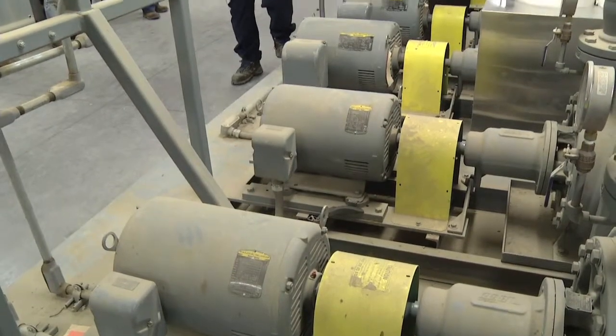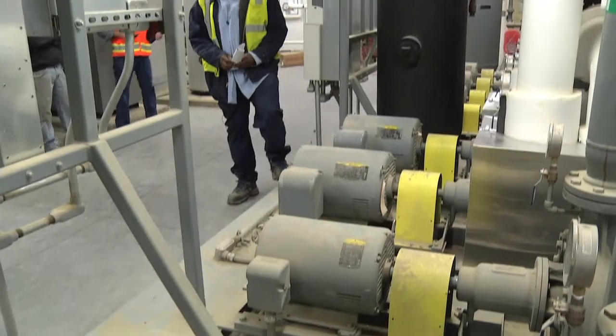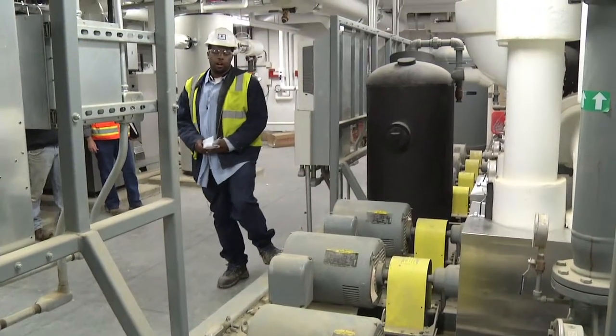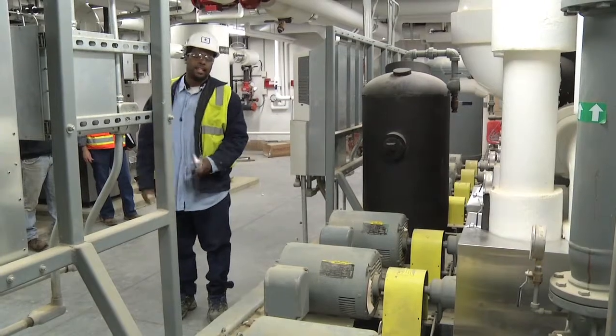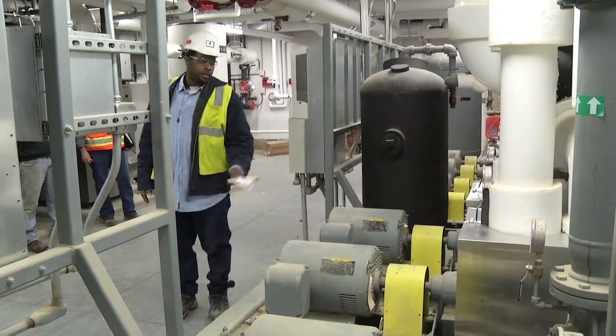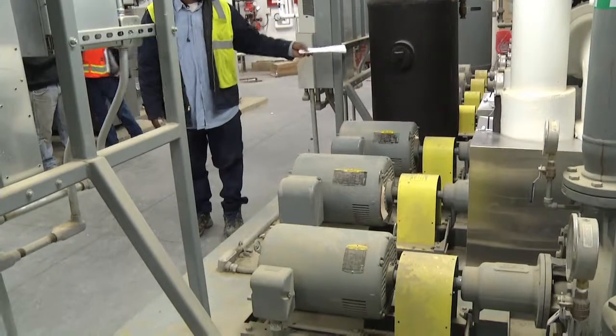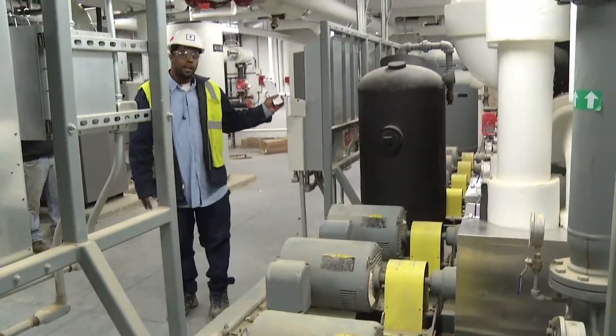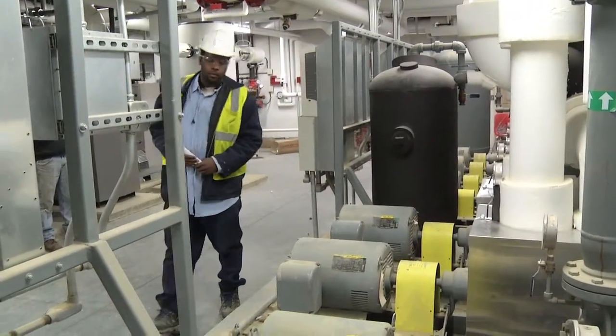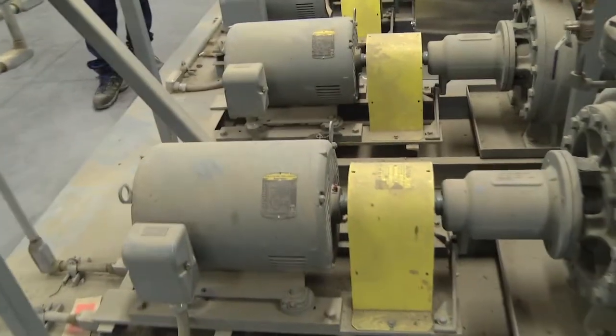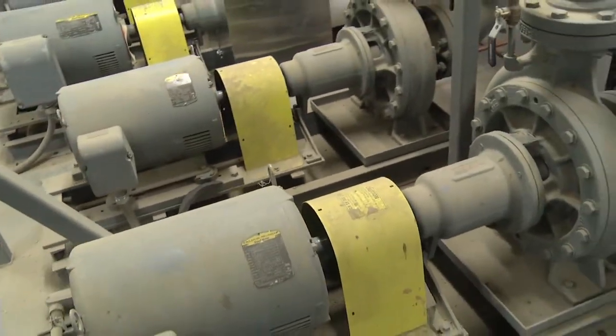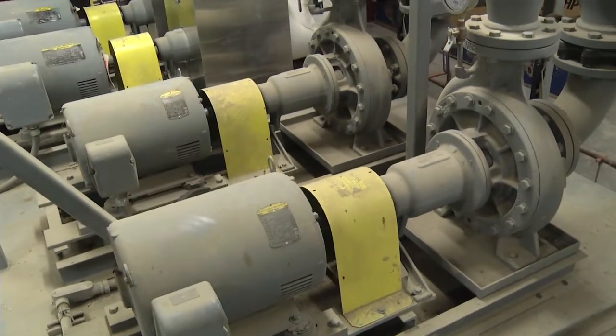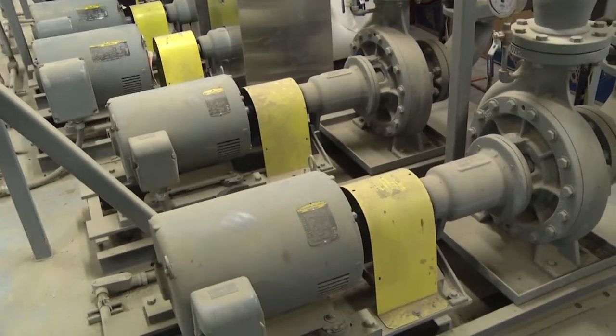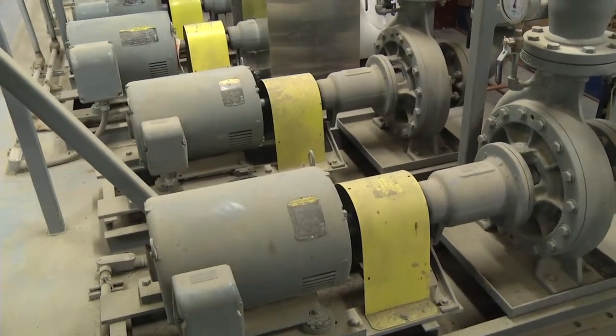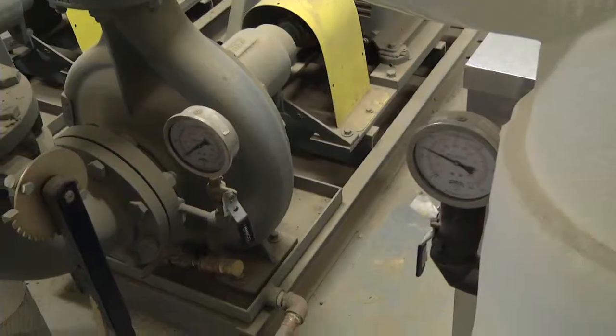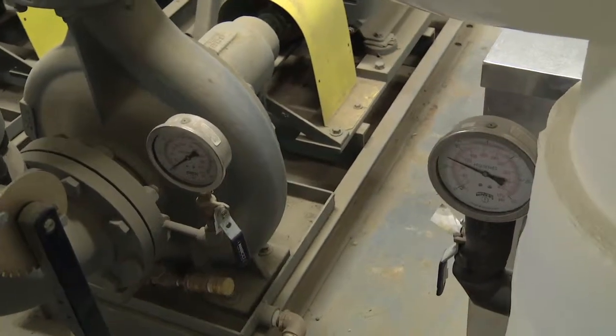And what we're talking about now is your hydronic pump packaging system, which consists of a lead lag, condenser pumps, primary chill water pumps, secondary chill water pumps, and hot water pumps. Each pump has its own ABB drive. They're set to run in a lead lag sequence. Each pump has a discharge pressure gauge on the outer side of the pump and a suction side gauge on the front side of the pump.